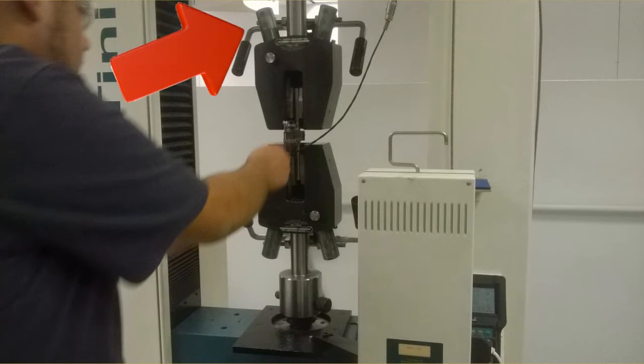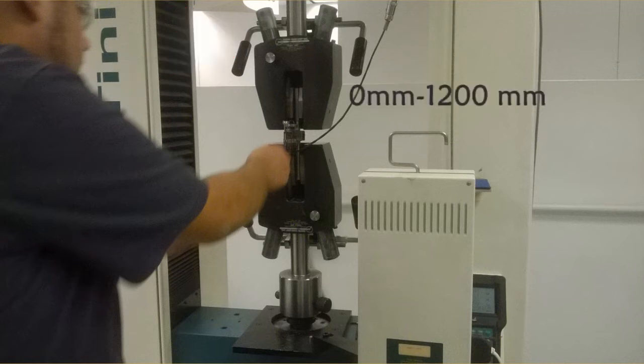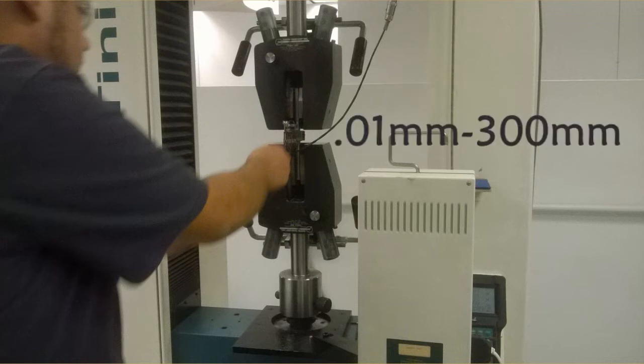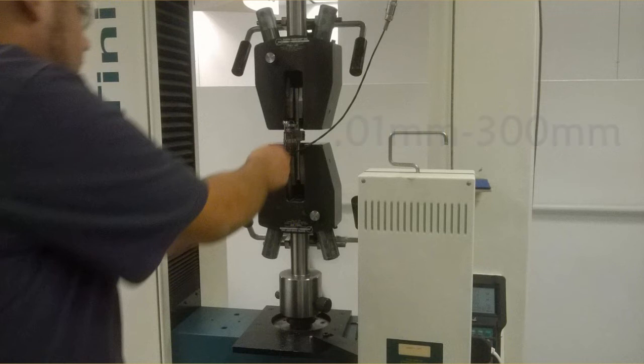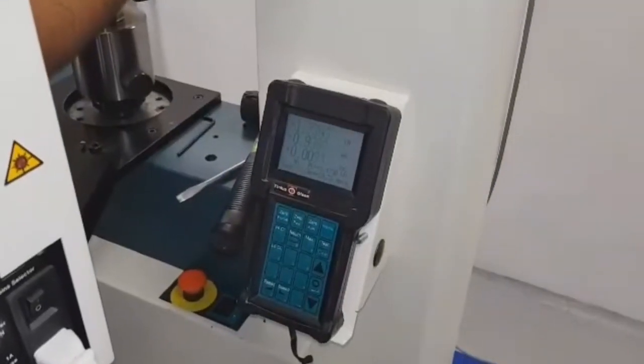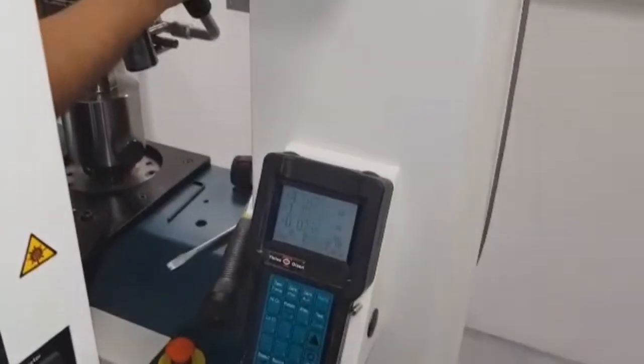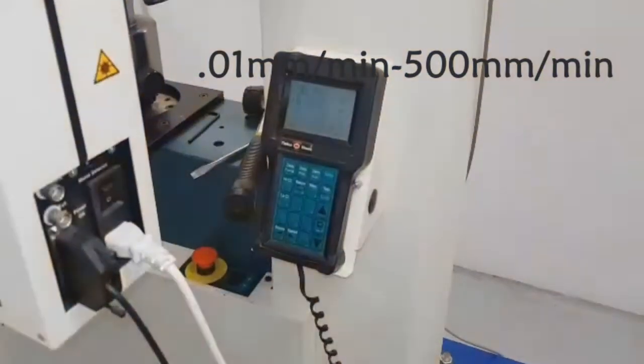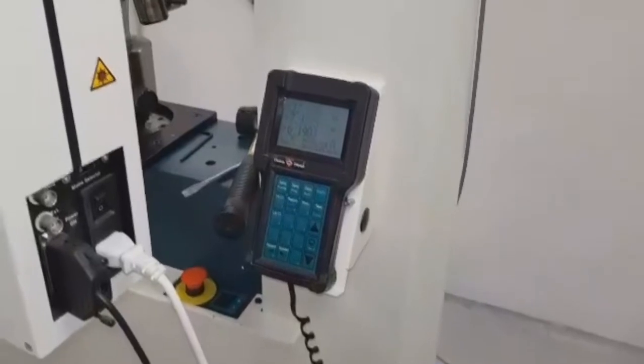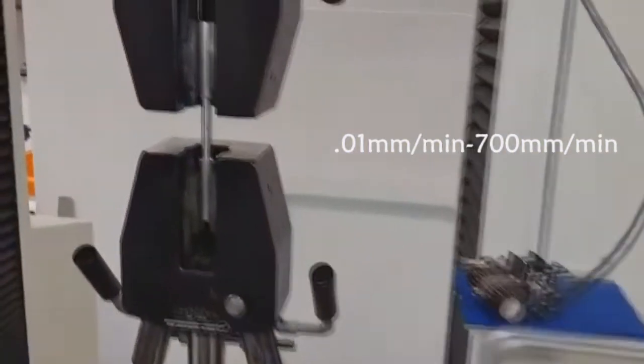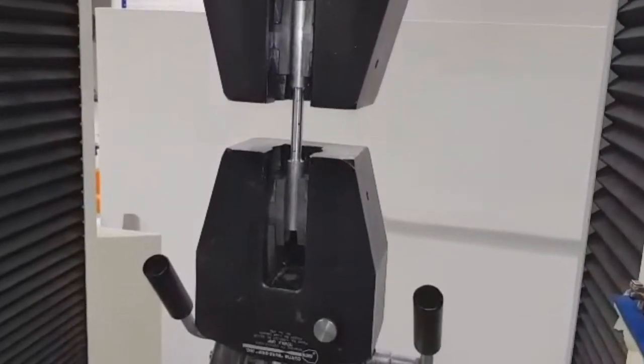The Tensile H300KU has a load cell of 60,000 pounds and an extension measurement range of 0 to 1,200 millimeters with a resolution of 0.0001 millimeters, with accuracy of 0.01 millimeters to 300 millimeters. The speed control has a testing speed range of 0.01 millimeters per minute to 500 millimeters per minute. The return speed is 0.01 millimeters per minute to 700 millimeters per minute.